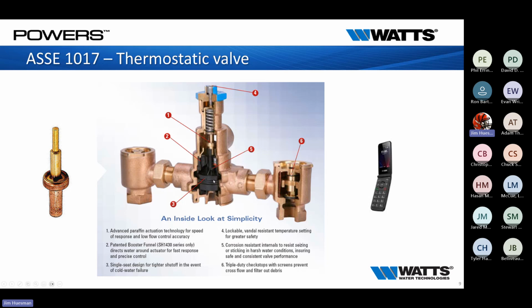You actually get hard water deposits built up on these O-rings, which won't allow this to slide. Large calcium buildups on our element again don't allow it to expand and contract. What happens then is we have a large fluctuation in temperatures up and down, back and forth, because this thing is just stuck in a position and won't work at all.